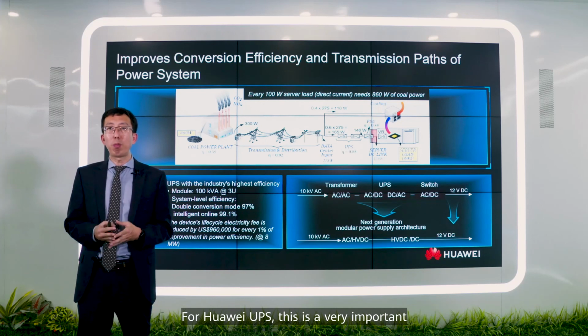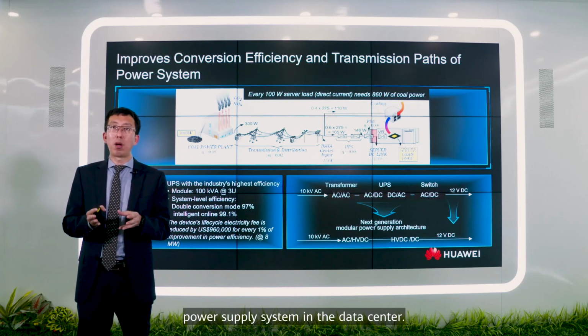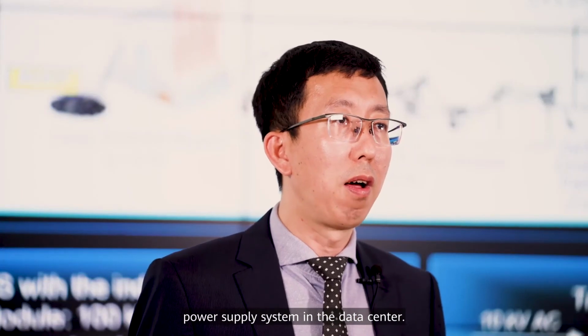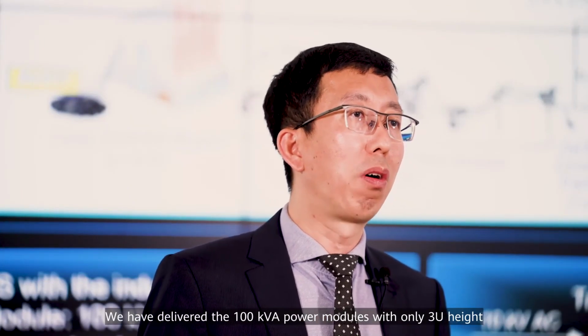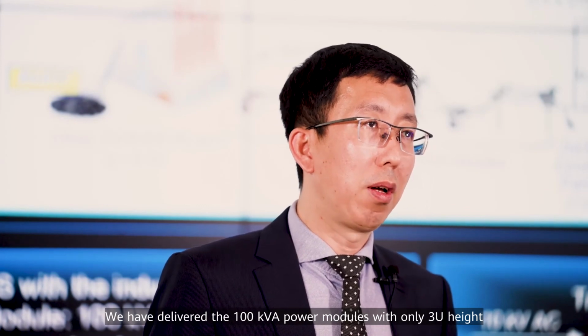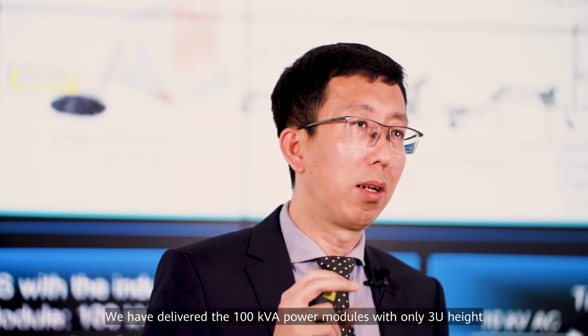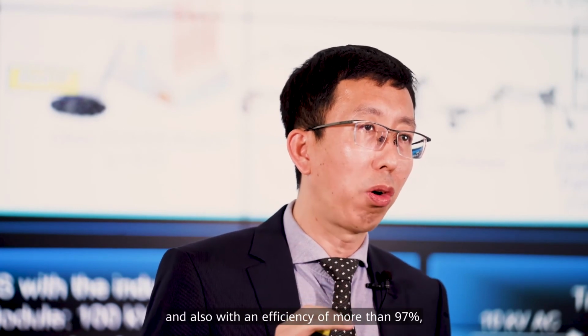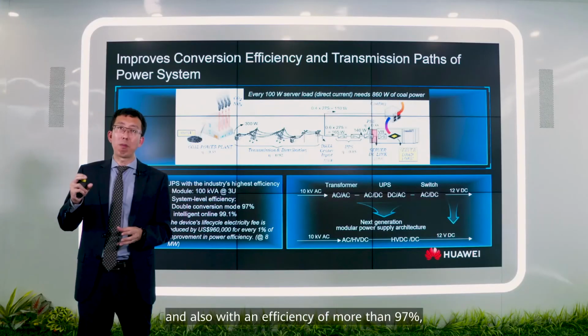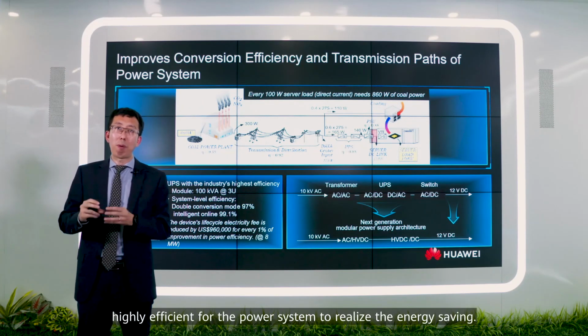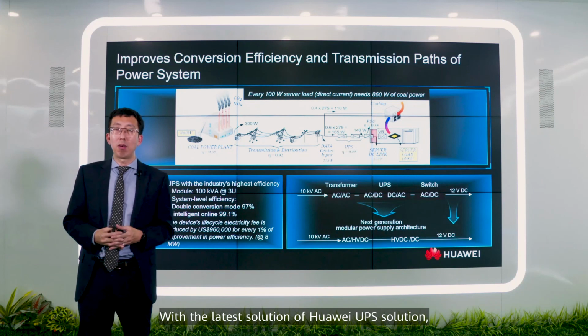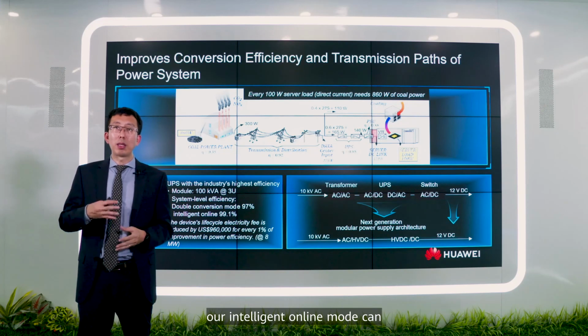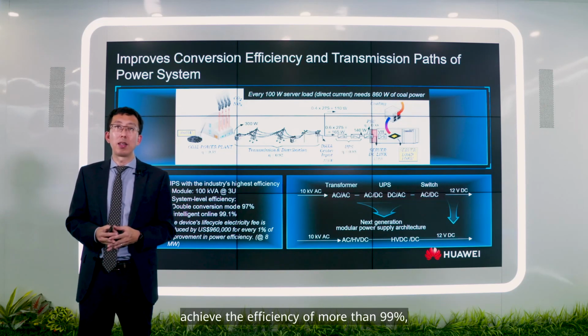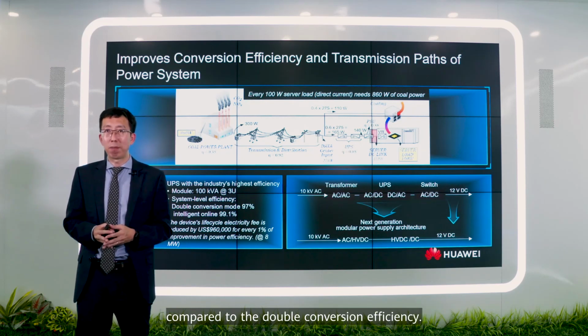From Huawei UPS, a very important power supply system in the data center, we have delivered 100 kilovolt ampere power modules with only 3U height, the highest density, and efficiency of more than 97%, the highest efficiency for the power system to realize energy saving. With our latest Huawei UPS solution, the intelligent online mode can achieve efficiency of more than 99%, compared to double conversion efficiency.